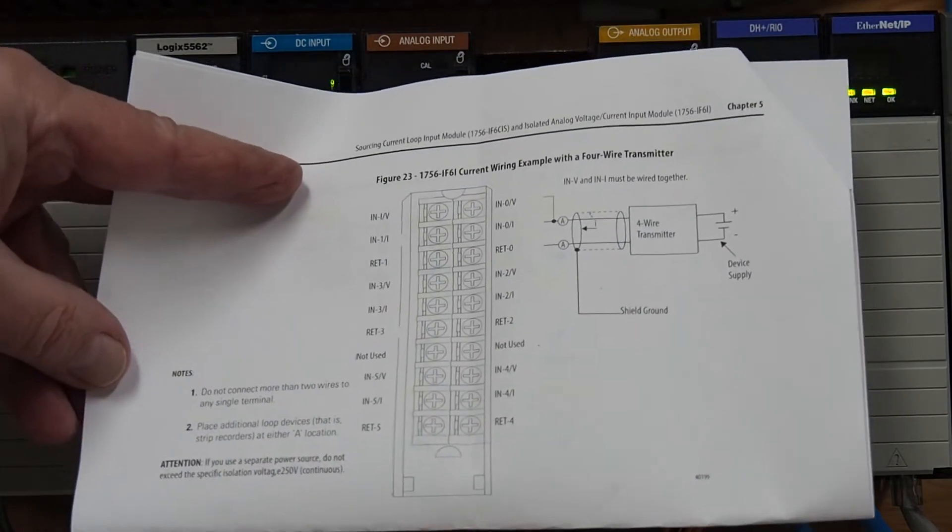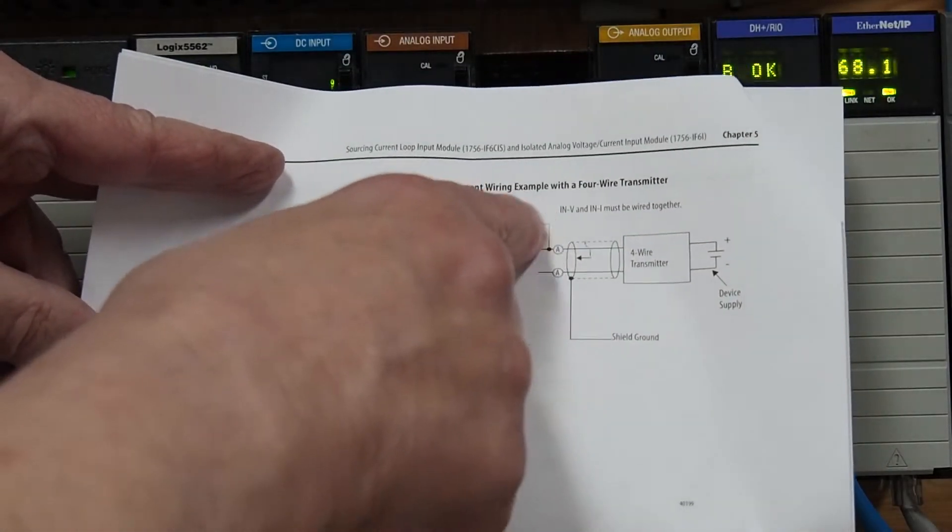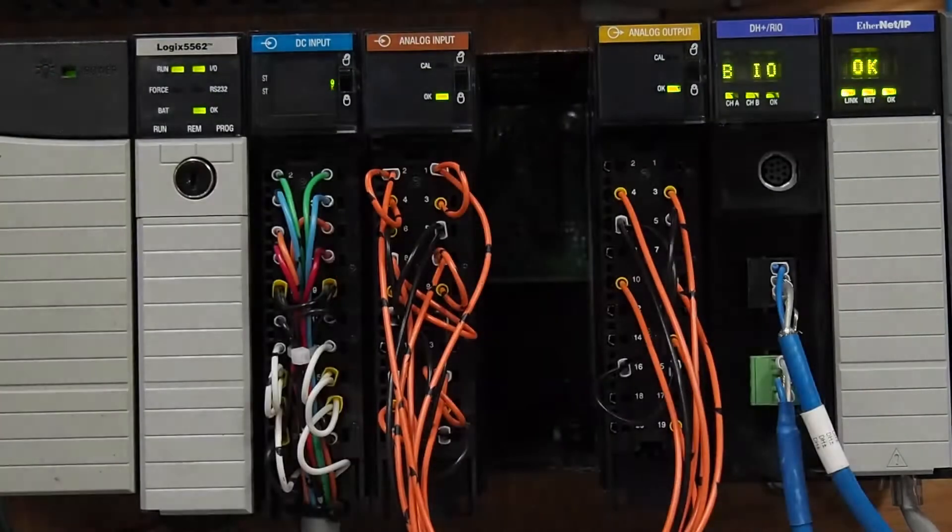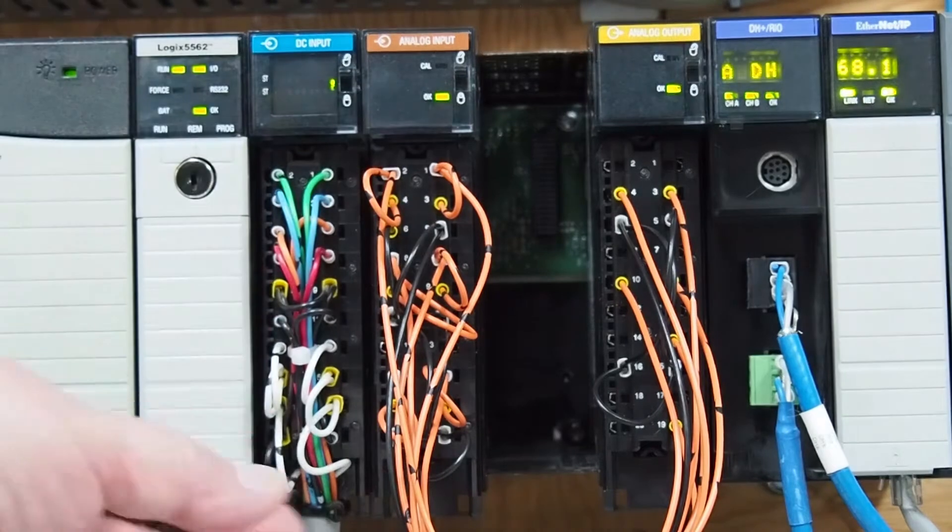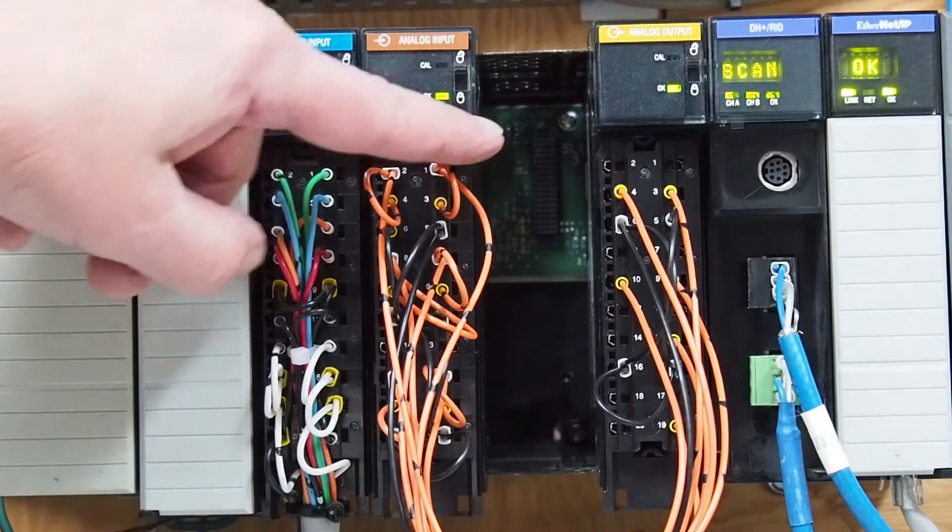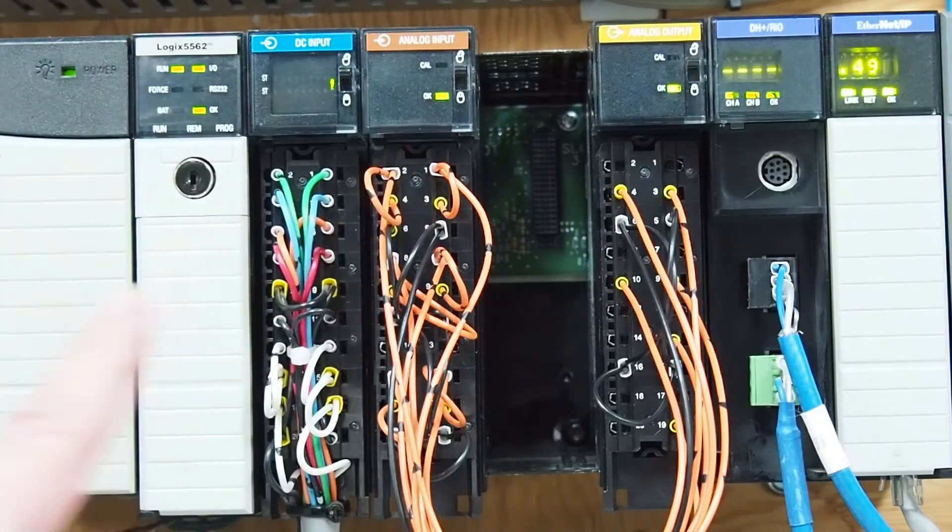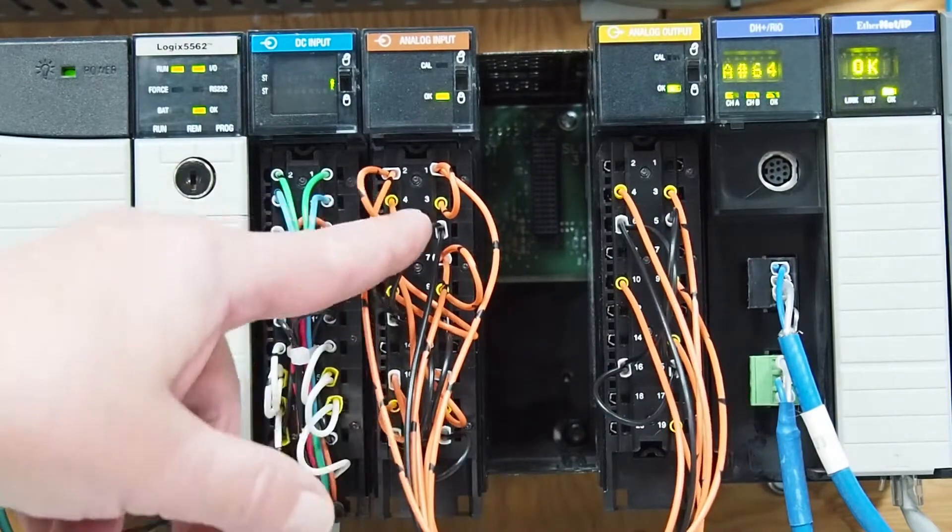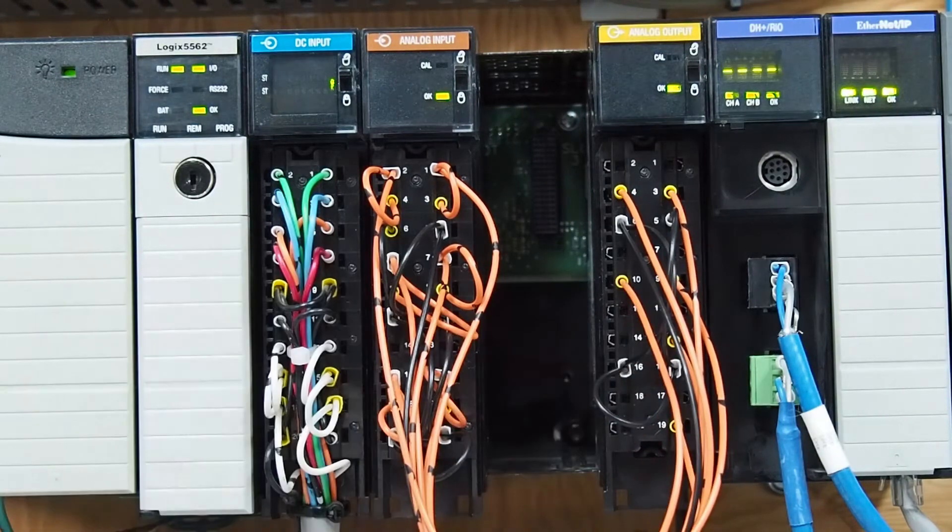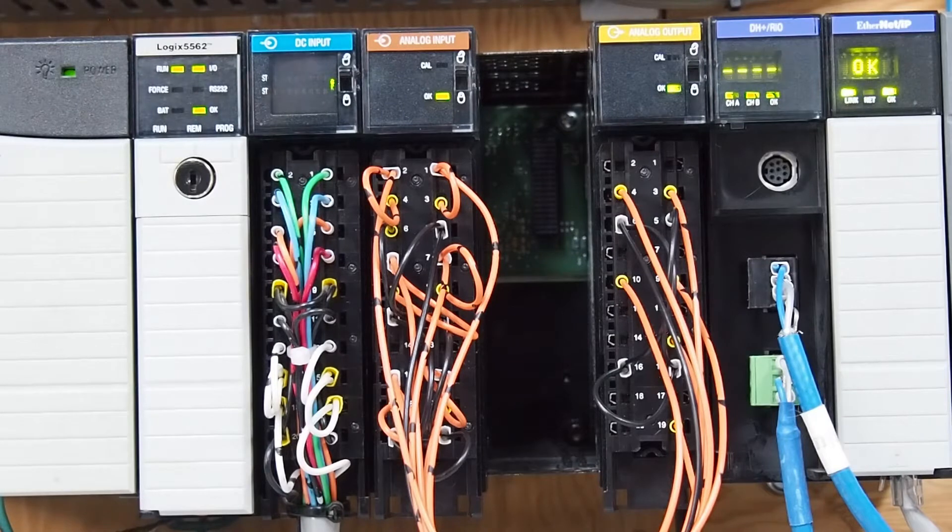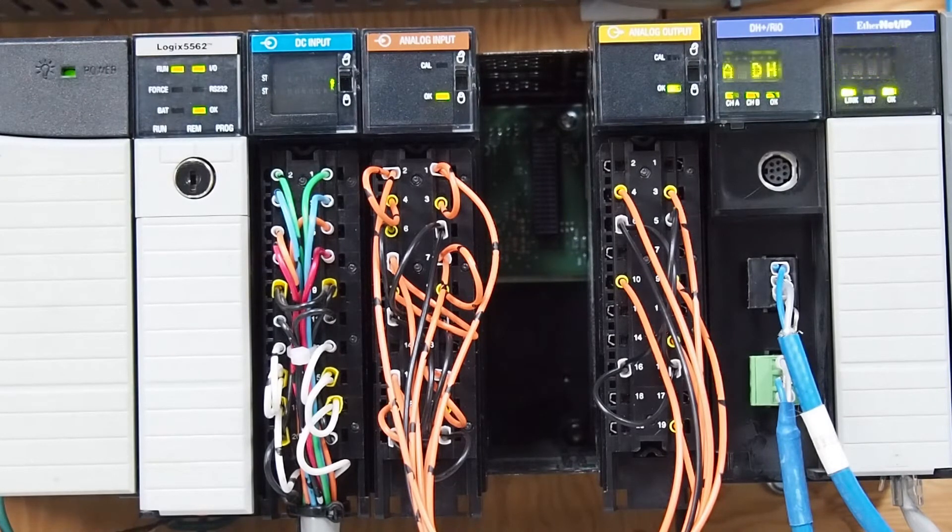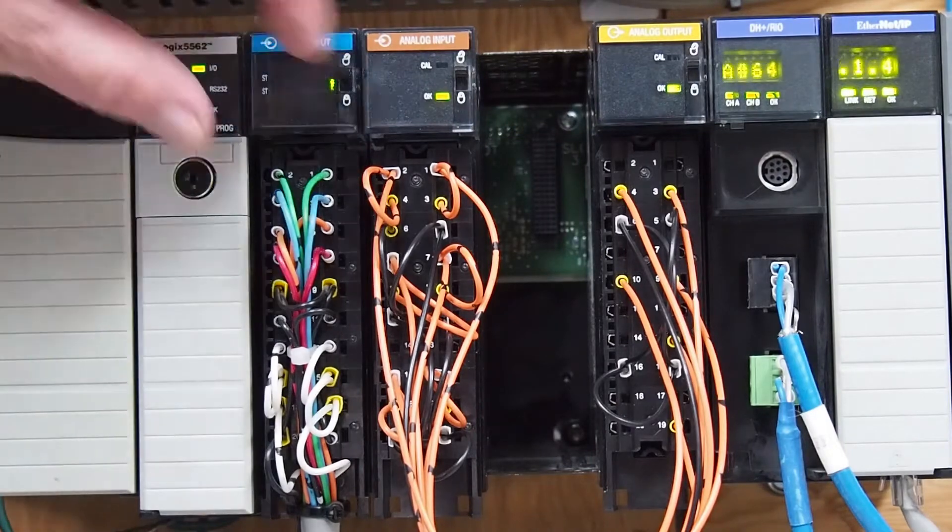And this is the page that shows the current module wiring that shows the jumper between for channel 0, and it's the same on every module. So there's our jumper. Now, this being an isolated module, you could have current on one channel, voltage on the others, because all of the commons are isolated. But what I've done for testing purposes is all of the commons are jumpered together on this card to this card. It's just not a recommended practice, but for testing on a bench, there's nothing wrong with it. So that's the current milliamp wiring.